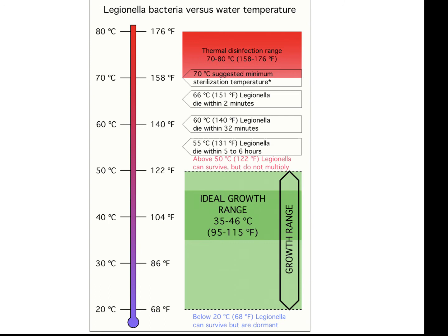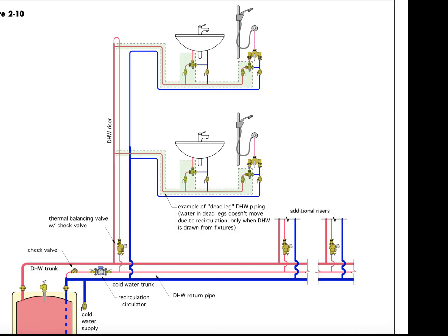The standards by which the distribution system are scalded dictate that it happen at about 2 o'clock in the morning when the potential for hot water use is at a minimum, and that the temperature of availability be maintained long enough to be able to kill off all of the bacteria, and it typically occurs once every 24 hours. This drawing depicts the distribution system whereby the hot water can be sent out to scald, sanitize the hot water supply mains as well as the circulation return mains.